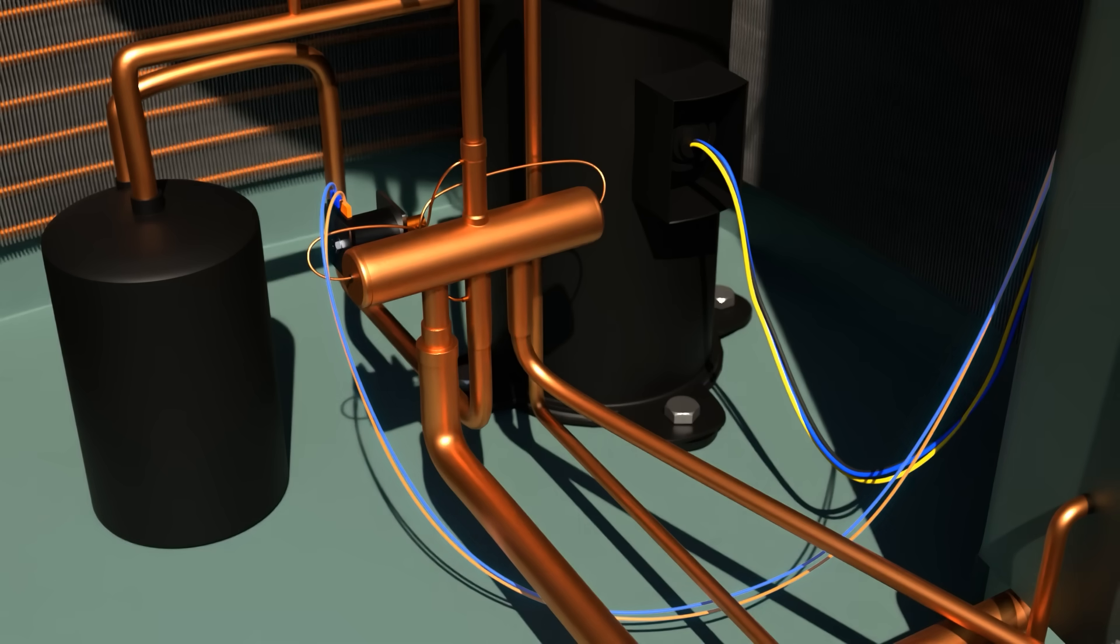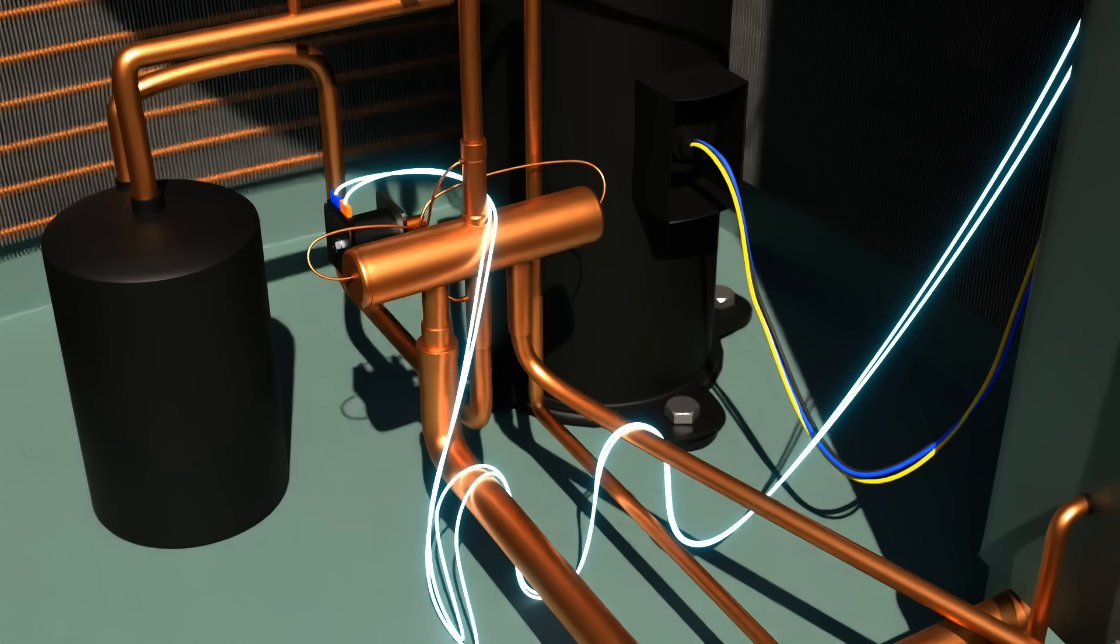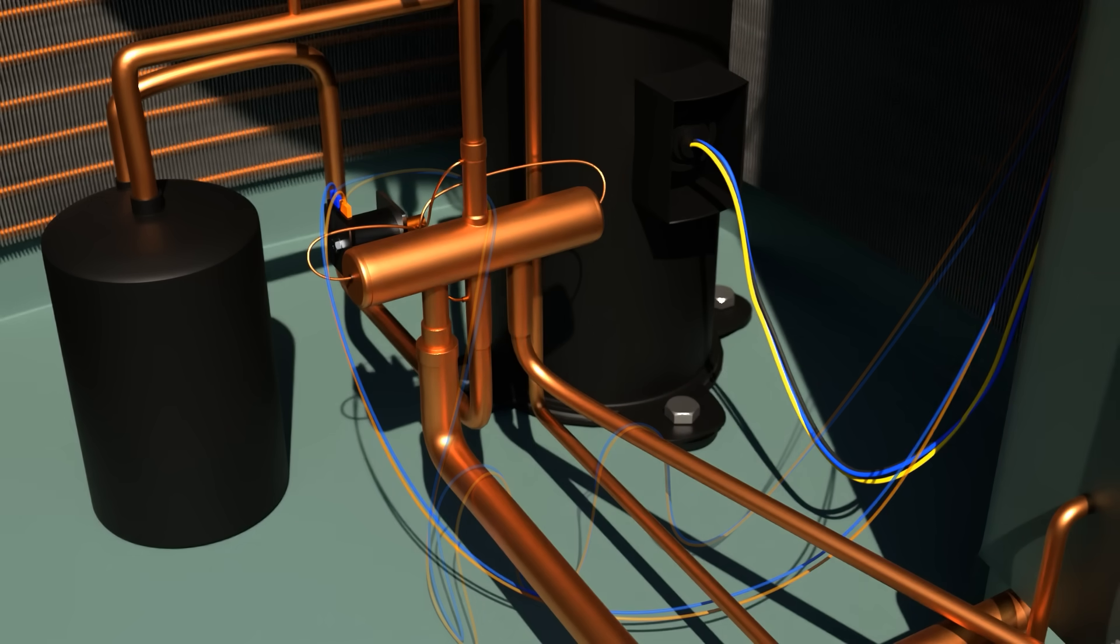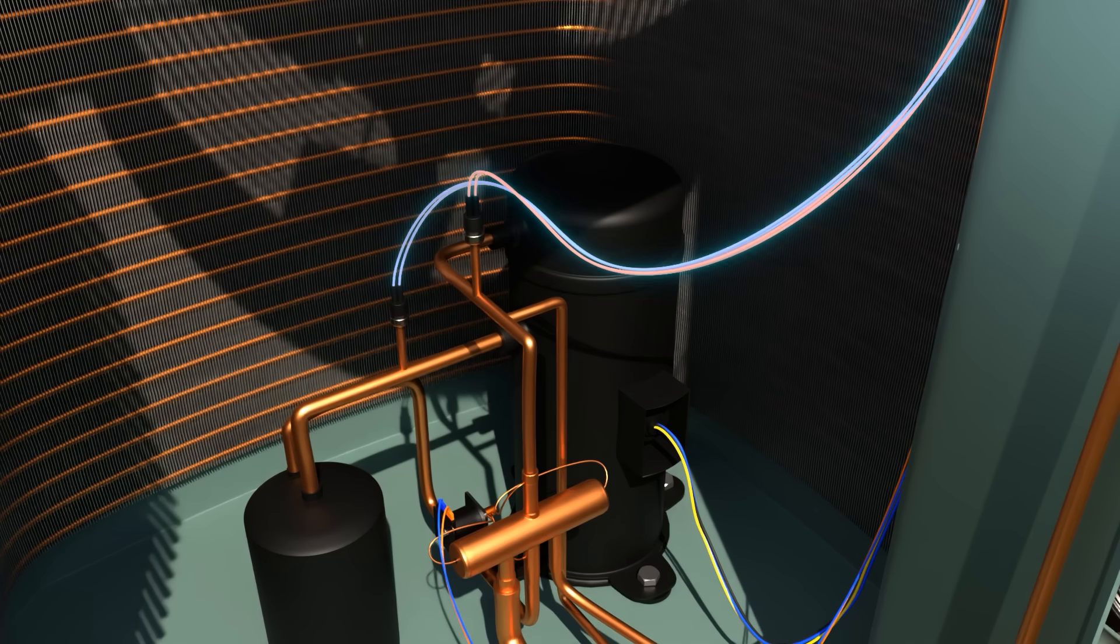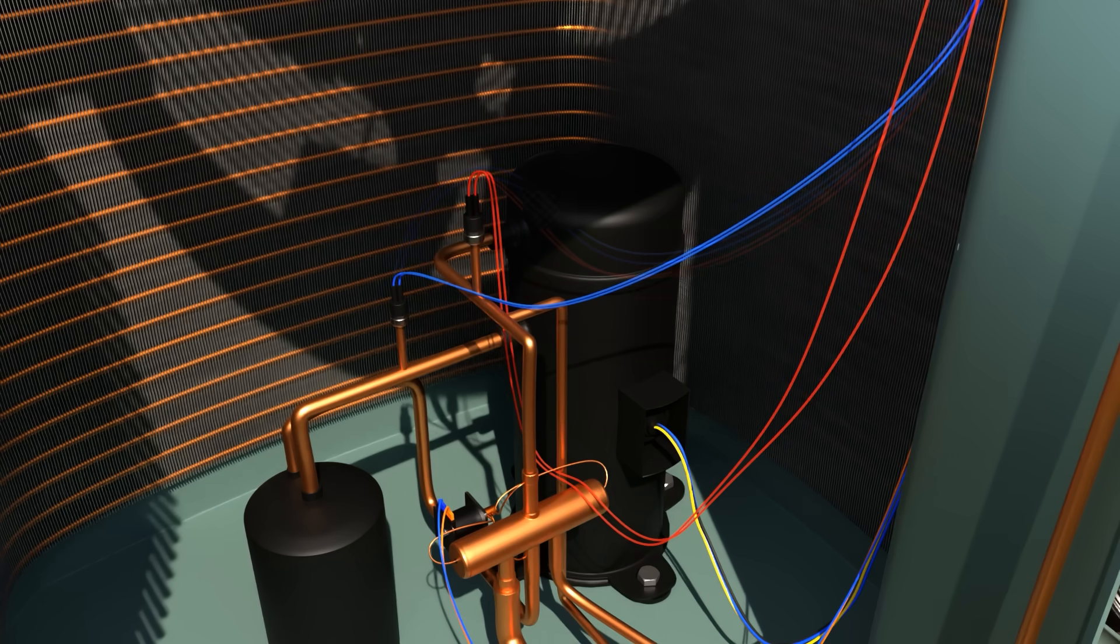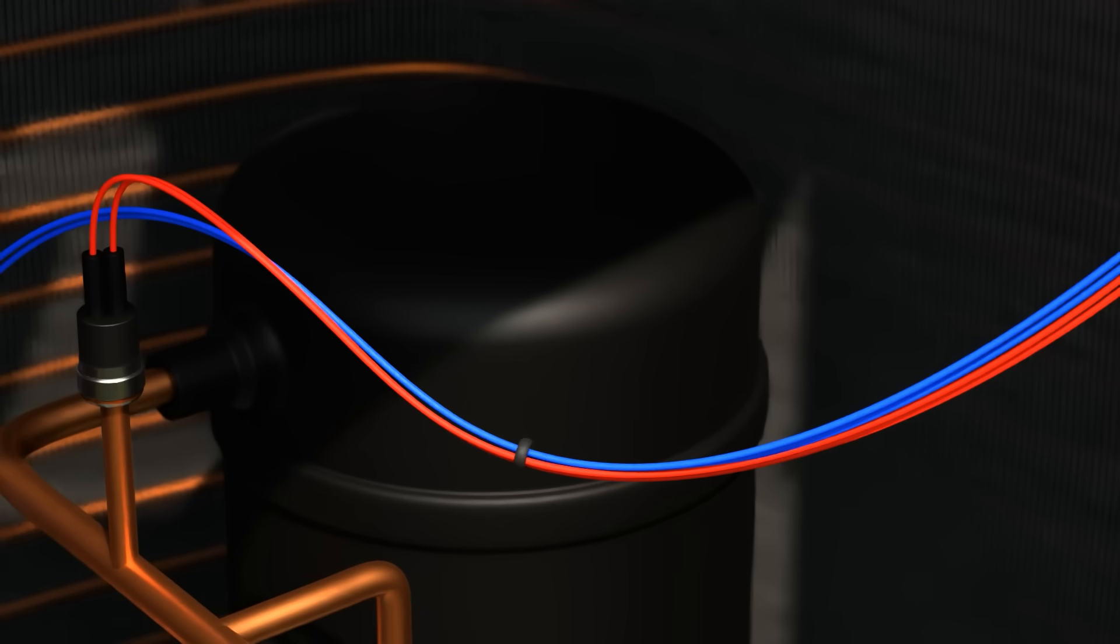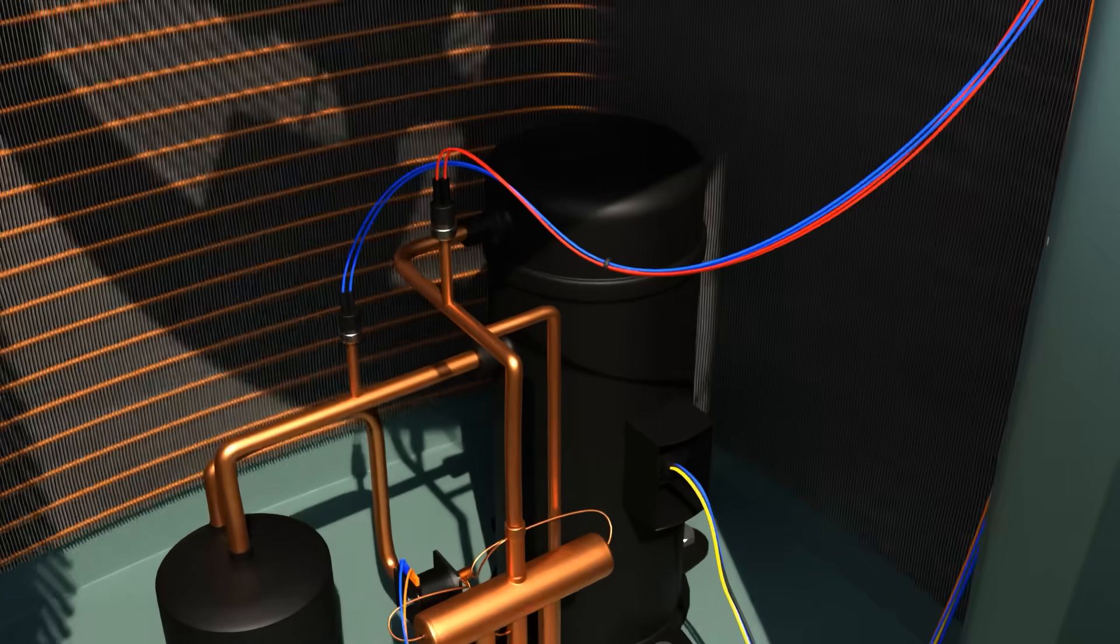The same thing is true of our electrical conductors inside our condenser. Ensure that they're not rubbing on top of metal parts or copper tubing where they can become damaged. When needed, use zip ties or other standoffs to secure conductors so they don't chafe.